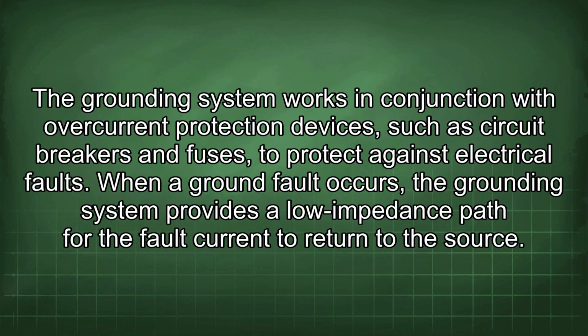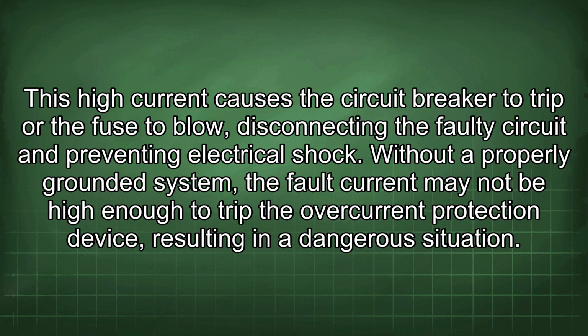The grounding system works in conjunction with overcurrent protection devices, such as circuit breakers and fuses, to protect against electrical faults. When a ground fault occurs, the grounding system provides a low impedance path for the fault current to return to the source. This high current causes the circuit breaker to trip or the fuse to blow, disconnecting the faulty circuit and preventing electrical shock. Without a properly grounded system, the fault current may not be high enough to trip the overcurrent protection device, resulting in a dangerous situation.